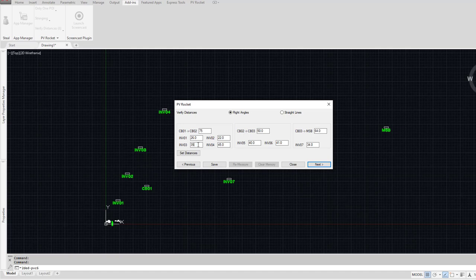The reason we put this box up there was one time I did a project where we had two panels side by side in plan view. So it measured them at 3 feet apart. But in reality, they were like 100 feet apart because one of them was on the wall outside the building and the other one was on the roof of a 4 or 5 story building. And it had to go through the building. It couldn't just drop straight down. There wasn't a straight chase, so it had to go over to a stairwell and then come down and then over. And so it ended up being kind of crazy, having to redo a lot of our calcs manually by hand, which is no fun. So we developed this box for that purpose.